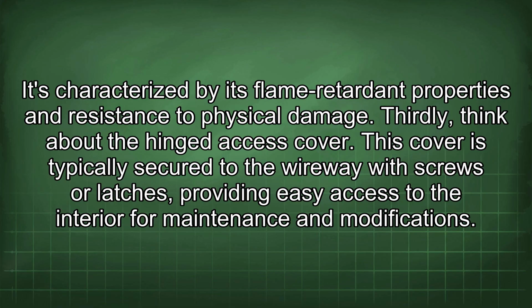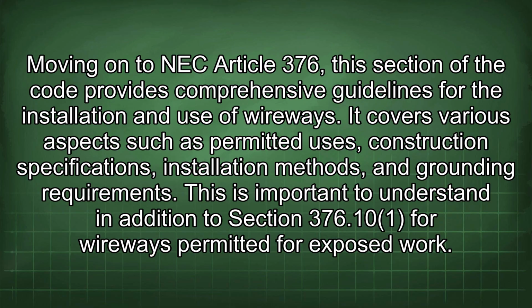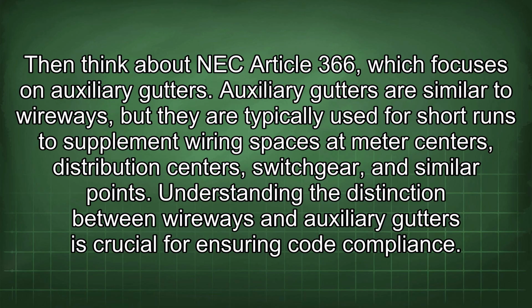Moving on to NEC Article 376, this section of the code provides comprehensive guidelines for the installation and use of wireways. It covers various aspects such as permitted uses, construction specifications, installation methods, and grounding requirements. This is important to understand in addition to Section 376.10(1) for wireways permitted for exposed work. Then think about NEC Article 366, which focuses on auxiliary gutters. Auxiliary gutters are similar to wireways, but they are typically used for short runs to supplement wiring spaces at meter centers, distribution centers, switchgear, and similar points. Understanding the distinction between wireways and auxiliary gutters is crucial for ensuring code compliance.